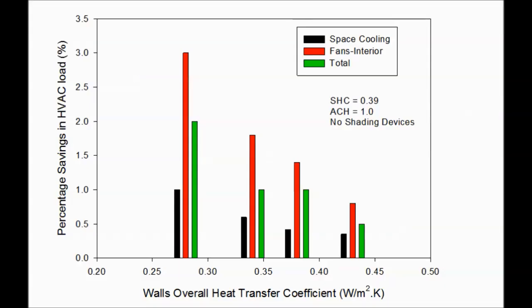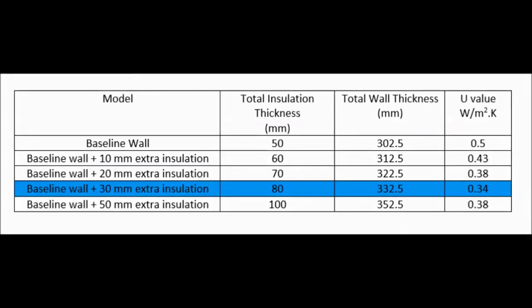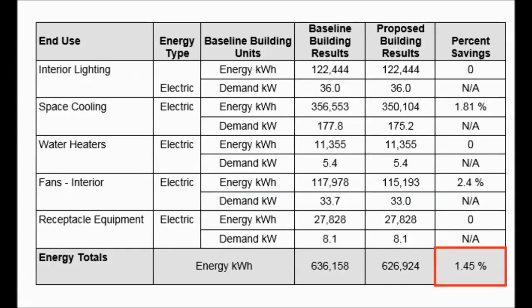The effect of U values on the percentage savings in the cooling load was studied prior to deciding a new value for the heat transfer coefficient. The figure shows a good relationship between lowering U value and savings in cooling load. The selected U value is 0.34, which corresponds to a wall section of the base model with an extra 30 mm of polyester insulation. The total energy savings due to using this new value is estimated to be 1.45%.